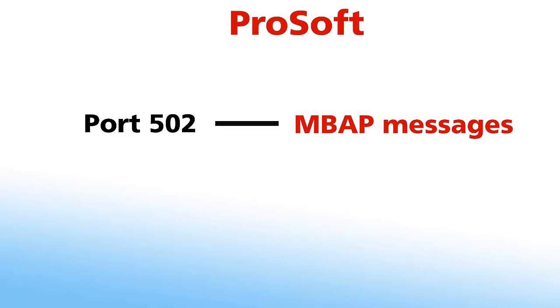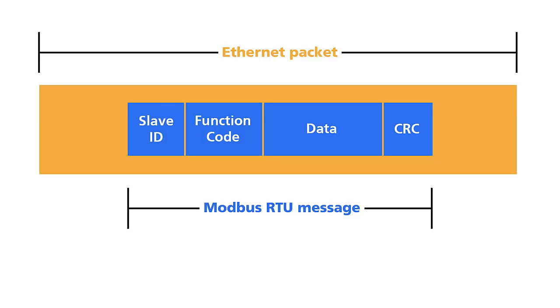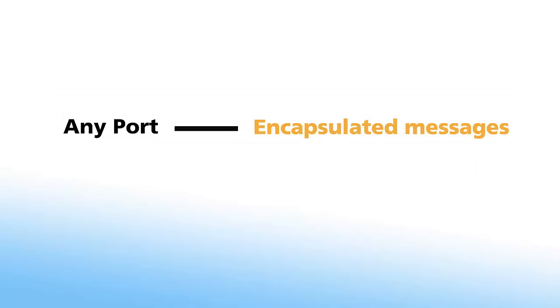Modbus uses port 502 for TCP IP communication. This is important if your data needs to go through a firewall. ProSoft uses that port for MBAP messaging specifically. Modbus serial messages can also be sent as regular RTU messages encapsulated inside an Ethernet TCP IP packet. Encapsulated messages can use any port, but ProSoft products are set to use port 2000 by default.